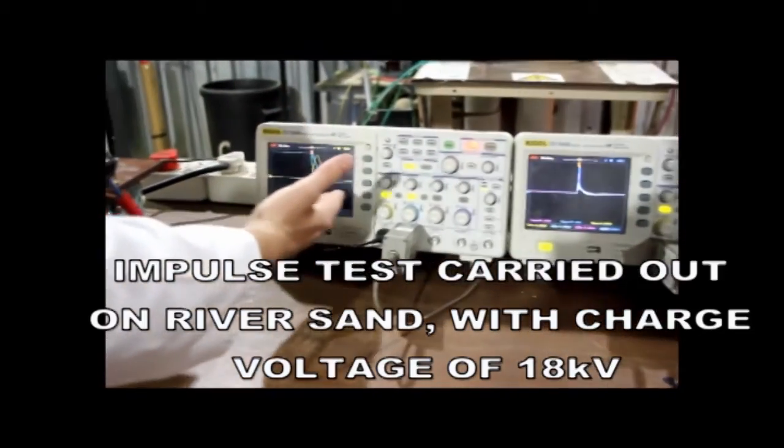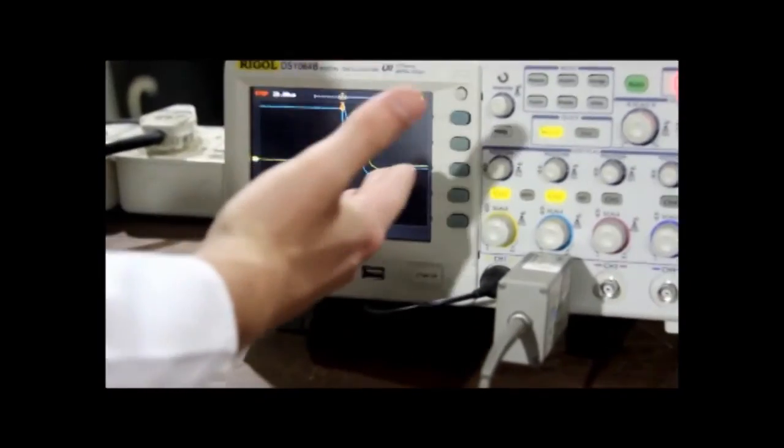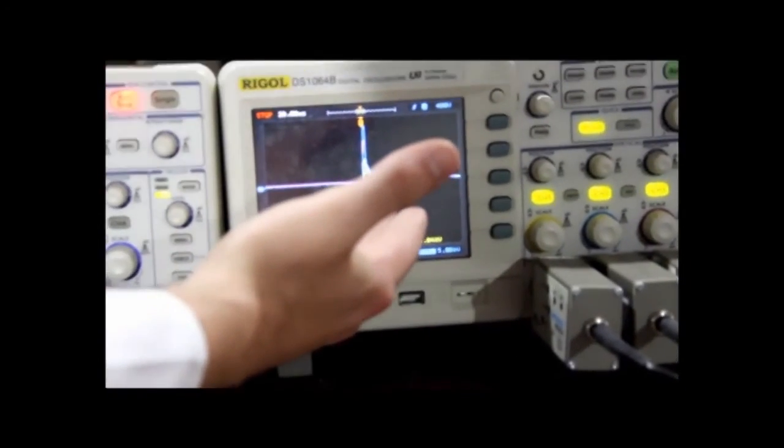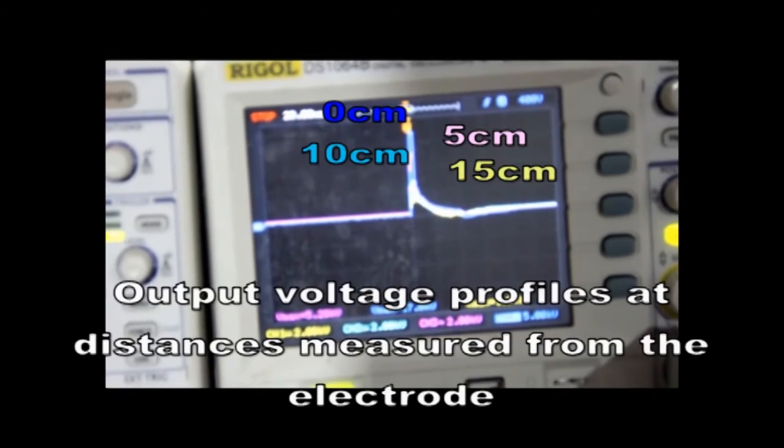Here, the blue line represents the charging voltage of the generator. The yellow line represents the current driven through the soil. And all these lines here represent the voltages measured at the various points within the soil.